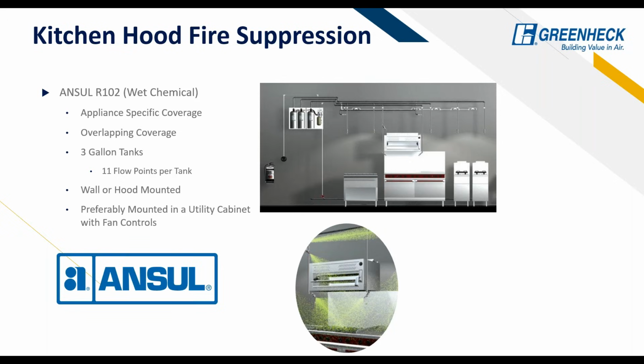And then kitchen hood fire suppression systems. So ANSUL R-102 is what we typically use. You can do appliance specific coverage, where if we know the appliances, we will size them at the factory as much as we can with the hood taps and all that according to the layout. With that said, what we get when we design the hood, that layout cannot change. The fires need to be where the fires were designed to be.